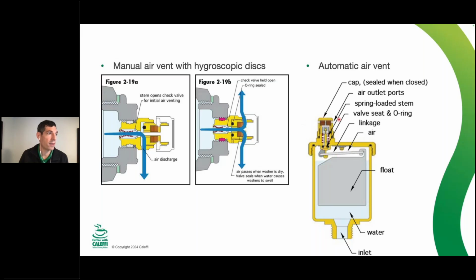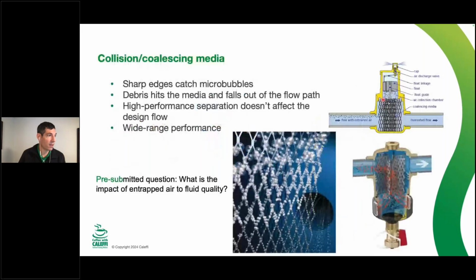So if you've seen an air vent that's dripping in your career, there's something hanging up that little needle valve right there, and we want to keep the potential for collision with that from other debris in the system minimized, and that's why we keep that little air pocket there. So once an automatic air vent has stopped venting air, just leave it. There's still a little bit of air in there. It may be a quarter of an inch, it may be 2 inches, depending on the size of the vessel, but we want that to stay separate from the water level at the top and the needle valve so it has the longest service life.